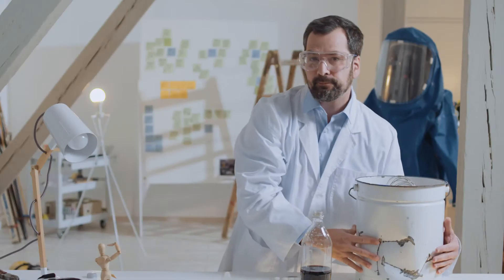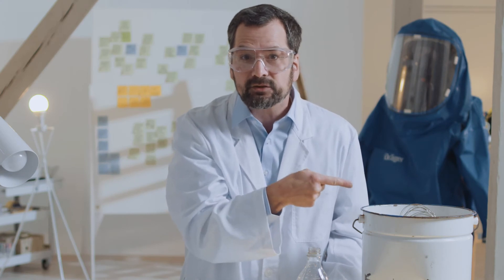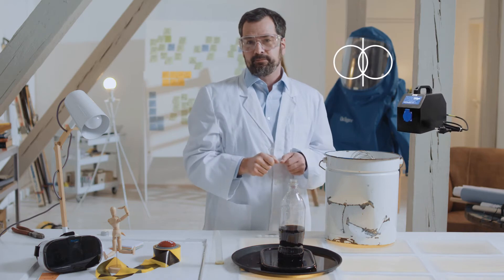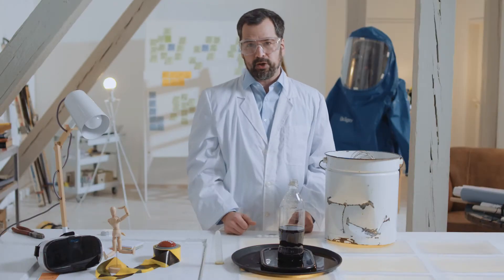That's why we should always use only certified electrical equipment. And now we come back to the little things with big impacts. To prevent this and to make my work safer, an isolating transformer must be used. It divides the circuit and inductively generates an earth-free circuit, which ensures that no electricity goes through the body. Keyword: Faraday cage.